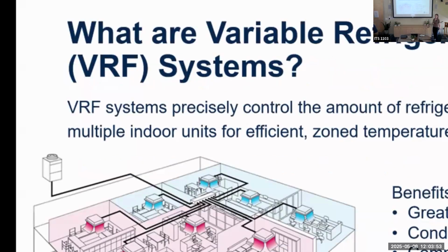A lot of you might be wondering, what are VRF systems? Not many people outside of HVAC are probably familiar with them or think about them ever in your life. But they are heat pumps. We've got one external heat pump outside the building that's supplying terminal units in each conditioned space or zone of the building by a refrigerant line. The refrigerant goes directly to that terminal unit instead of a bunch of air flowing to terminal units in each of those zones. So it's usually more efficient than a rooftop unit. It has more modularity or compactness, especially in historic buildings where you might have low roof space and can't really get large ducts in there. Having just a refrigerant line might be beneficial. You do still need some ductwork for your outdoor air supply, but less than what you typically need. You also have a heat recovery option where you can remove heat from spaces that are being cooled and transfer that heat to spaces that are requiring heating.